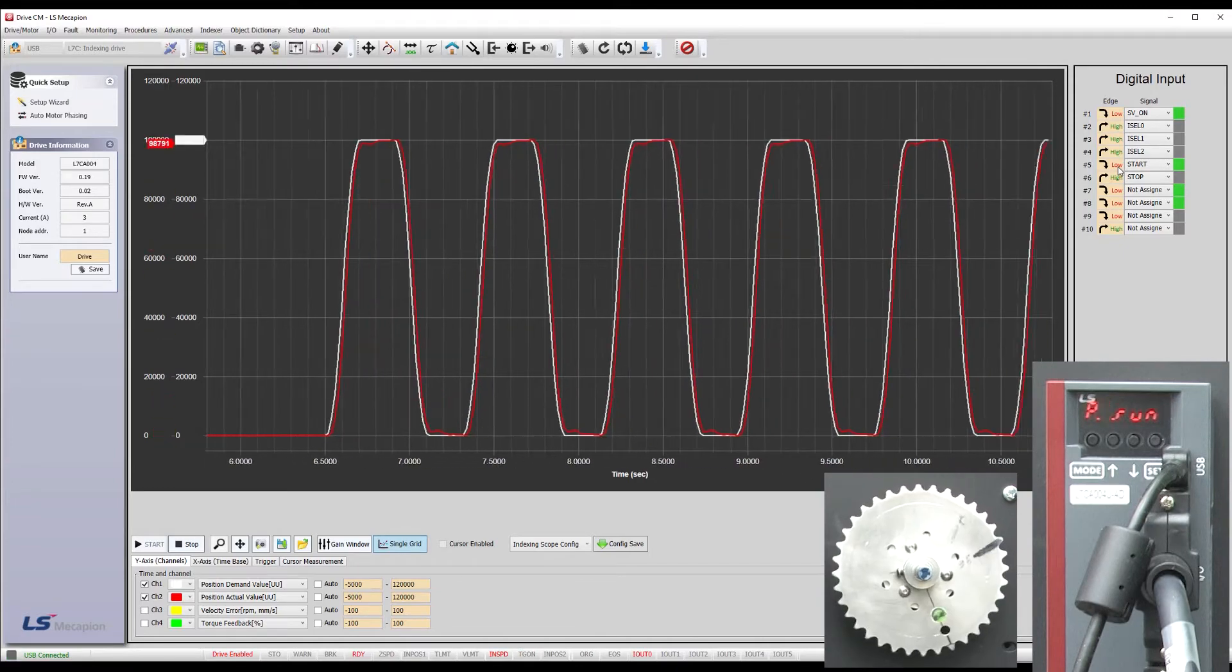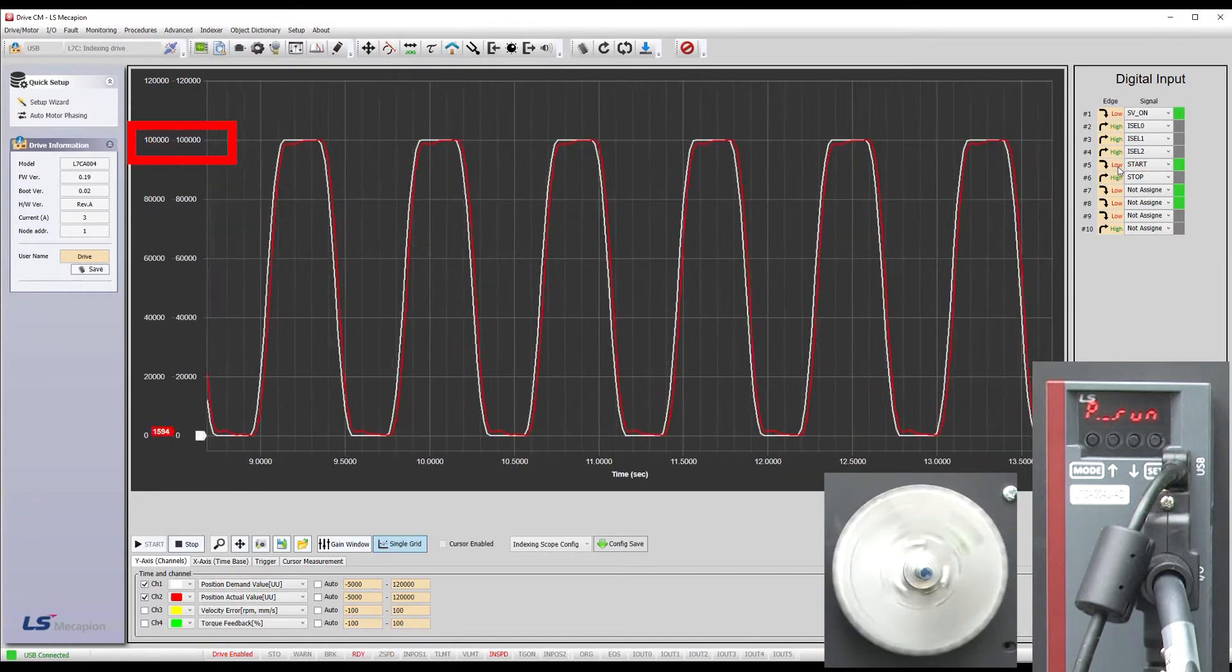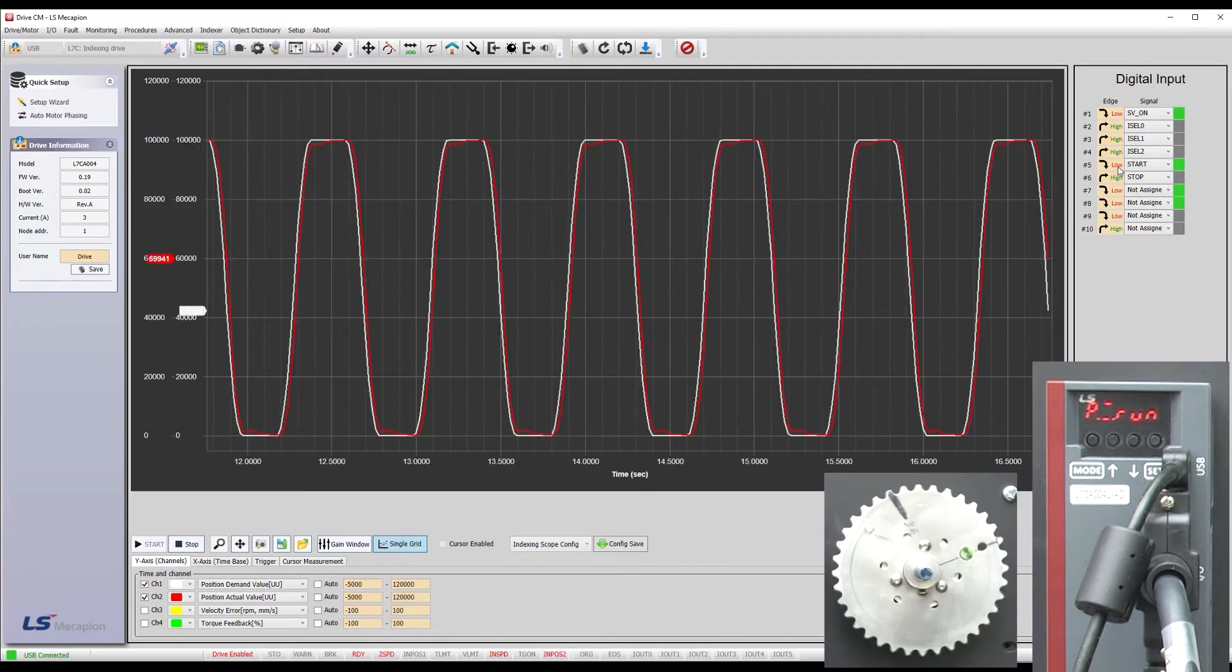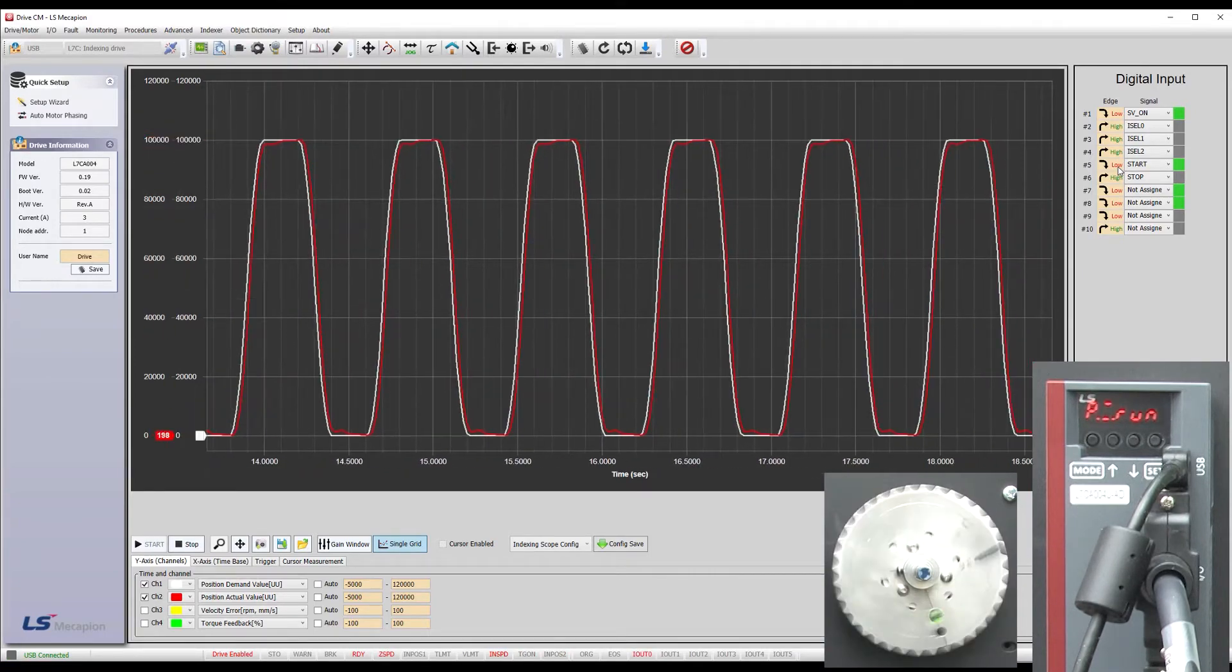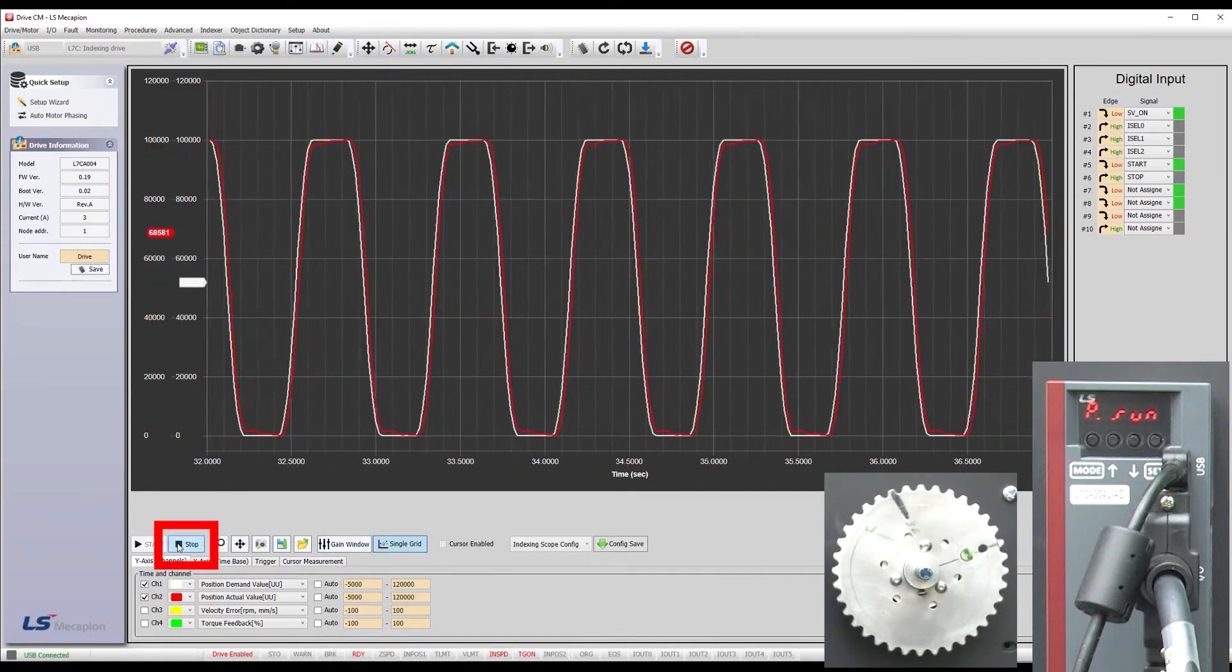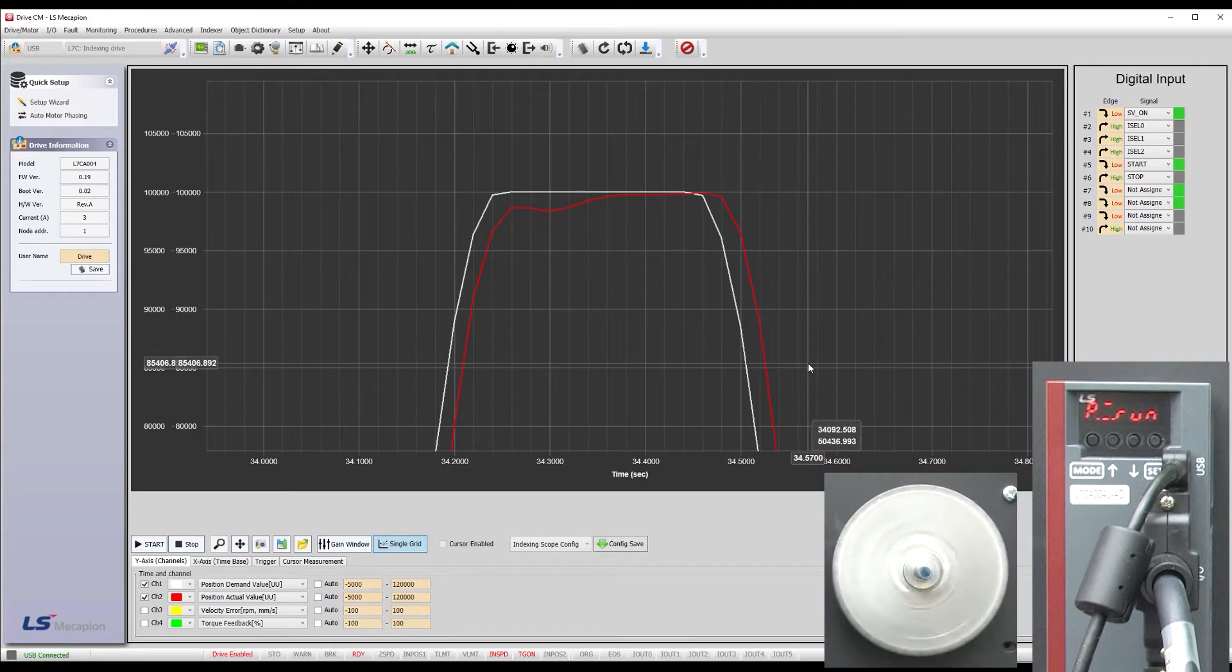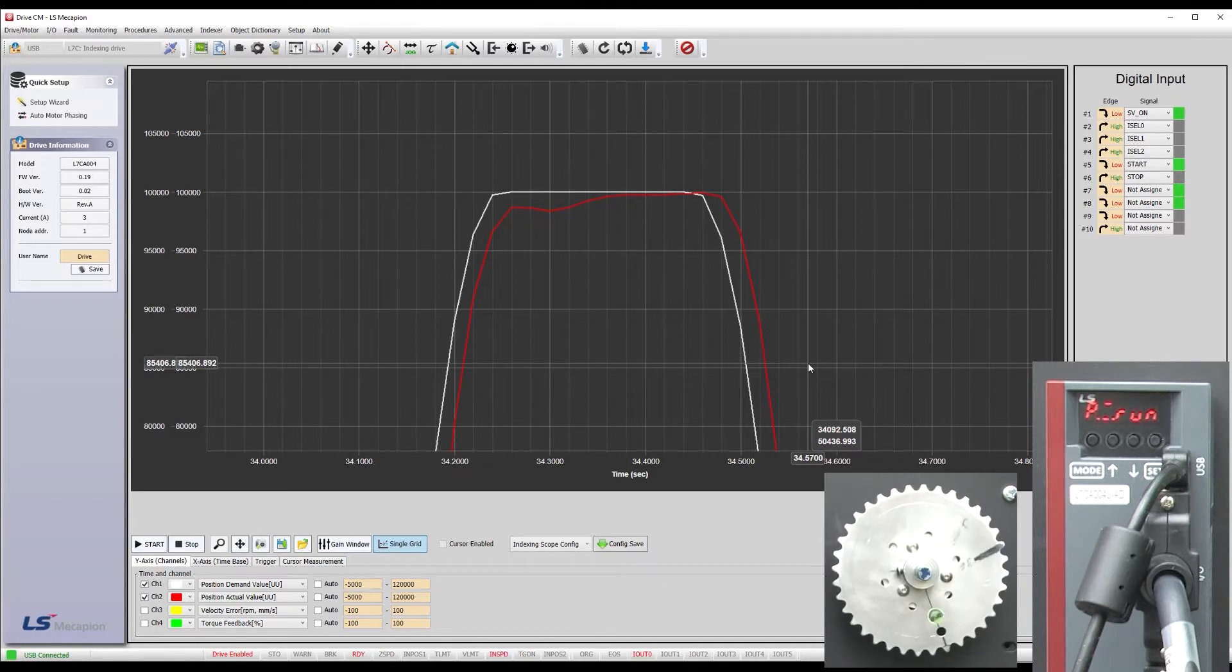Sure enough, we see the commanded position in white go out 100,000 user units, wait 200 milliseconds, then go back 100,000 user units, wait 200 milliseconds and repeat. If I stop the scope and zoom in, we also see the red actual position is basically tracking the commanded position, but not very well because the servo system hasn't been tuned yet.